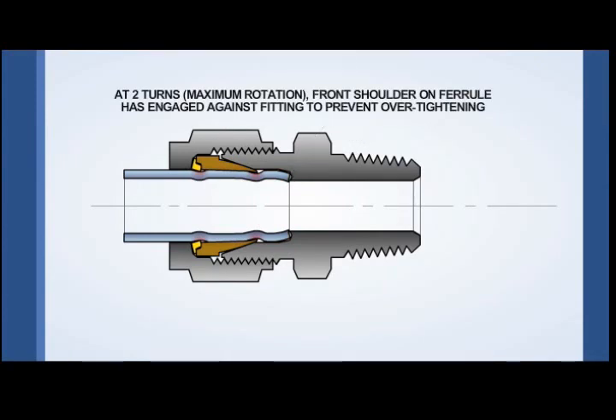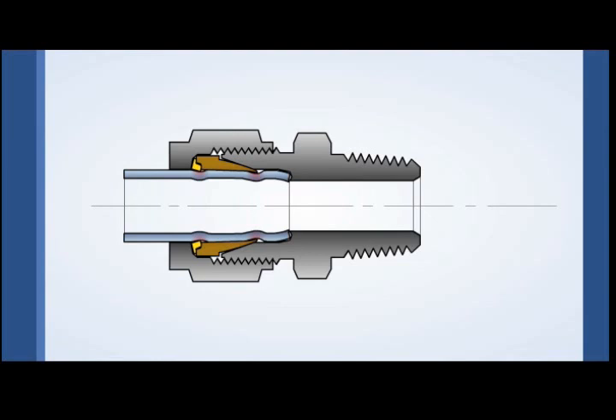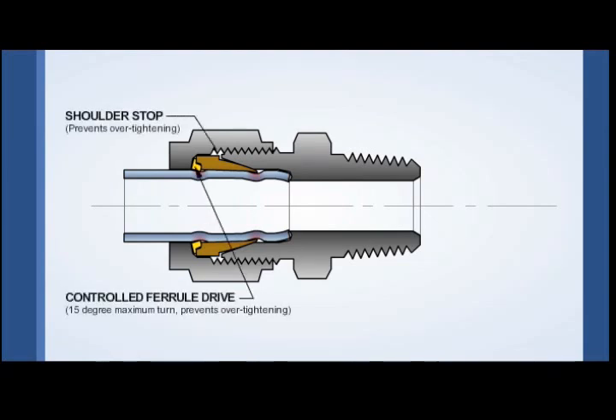At two full turns, the shoulder on the front ferrule will engage the fitting body to prevent over-tightening. With GyroLock, this shoulder stop plus the controlled 15-degree rotation of the rear ferrule avoids the issues associated with the most common mode of fitting failure: over-tightening.